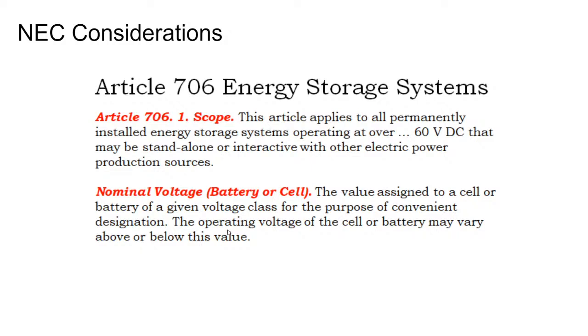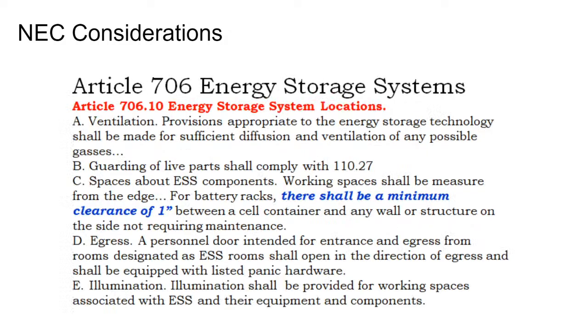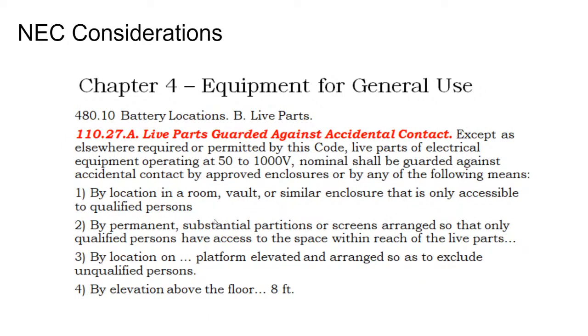There's a section for battery storage that applies to batteries over 60 volts. One way to get rid of some of the battery room protection requirements is to keep the system voltage low. We already talked about ventilation requirements. The battery should be 1 inch between the cell container and the wall or structure, usually taken care of by the battery case. But the important one is that you have to prevent accidental contact with the live parts.